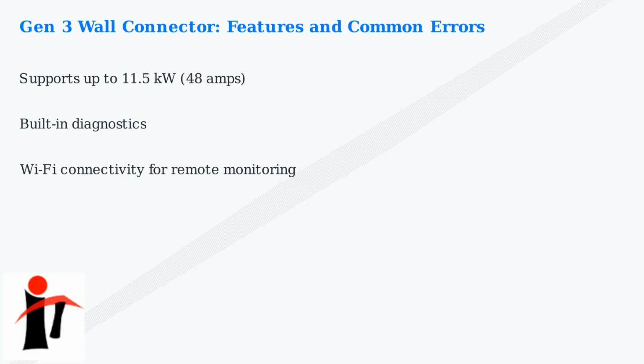Wi-Fi connectivity allows remote monitoring and control through the Tesla app, keeping you updated on charging status. It automatically senses the amperage and receives firmware updates over the air to handle voltage fluctuations and improve reliability. Now let's look at common errors that can occur with the Gen 3 wall connector. Common errors include cable fault or charger fault, often displayed on the vehicle touchscreen or app. These can often be resolved by simply unplugging the connector from the outlet and plugging it back in to reset the connection. If issues persist, check the wiring as shown in this diagram, ensuring proper connections for ground, L1 and L2 wires. Automatic firmware updates help handle voltage fluctuations, addressing many issues that affected older charging systems.